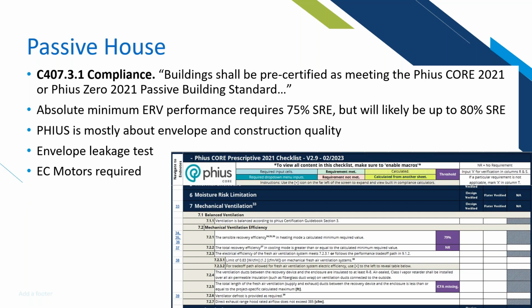Those checklists, by the way, in our stretch code and specialized code, identify it. C407.3.1 compliance says buildings shall be pre-certified as meeting the Phius Core 2021 or Phius Zero 2021 passive building standard. Within that standard, hearing from the engineers in the street, you can get an absolute minimum ERV performance requiring 75% SRE, but it'll likely be up to 80% SRE. That's the sensible recovery efficiency I mentioned earlier.